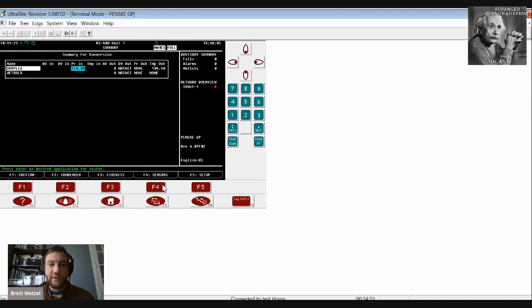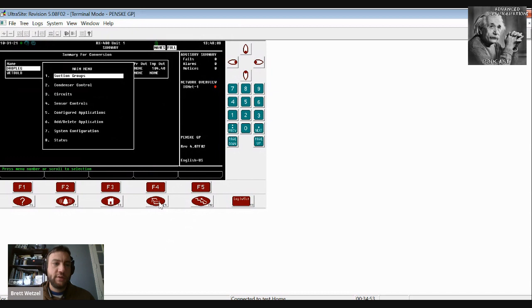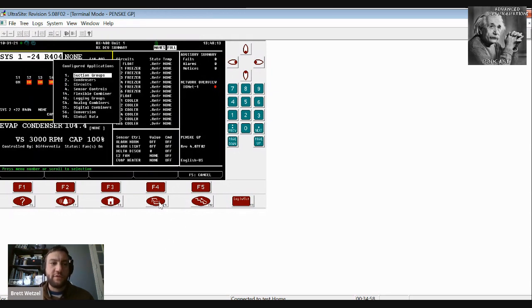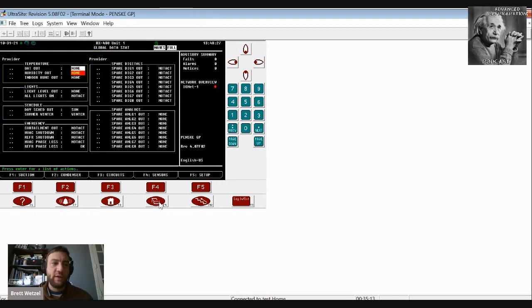So that's what conversion factor is. Menu, configured applications. You also have global data. This would be if you had another value, whether analog or digital, and you could transfer it from controller to controller via Ethernet. A lot of times they'll have the ambient temperature sensor or light level, especially if the light level sensor happens to be close to the refrigeration rack, but has to be transferred to an HVAC controller.